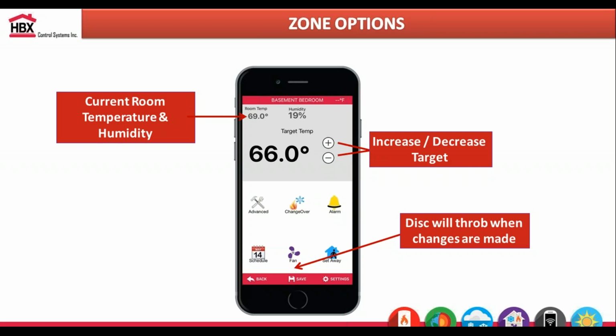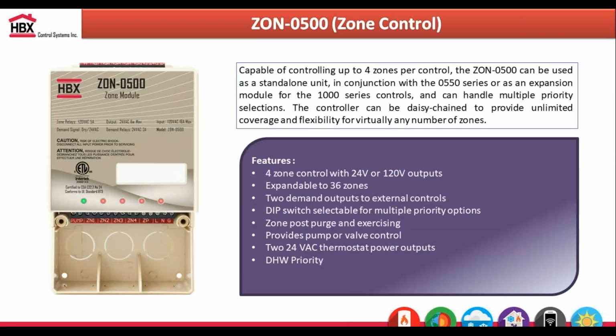There's auto changeover from heating to cooling, so it does it for you. You don't have to set it as a heat control for the winter and then cooling control for the summer. You can just put when you want your heating and cooling to turn on, and it automatically will change over for heating or cooling. In terms of schedule, you have weekend and weekday options, and then again you have that advanced settings where you can set up pretty much your entire system through the phone. You don't actually have to touch any of the thermostats as long as it's connected to Wi-Fi. So it's just all around a really cool system. Once you've used it once, most customers are very impressed about the functionality and how simple it is to program and wire just using our HYDRONIC network app.